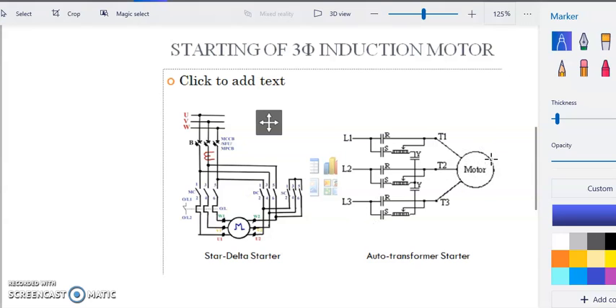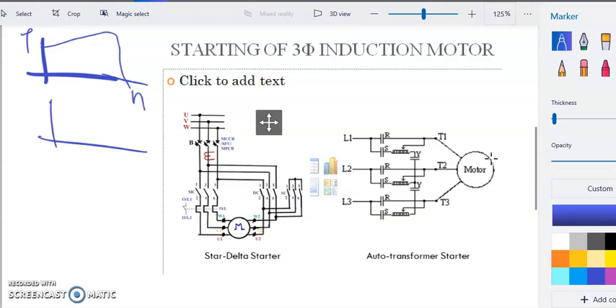So what happens is that when we start our motor, there will be an inrush current, which will be multiple times the rated current. If you plot the torque versus speed of your motor, it will be like this. But if you plot your current versus speed, there will be a spike. Your I load will be very high during starting.